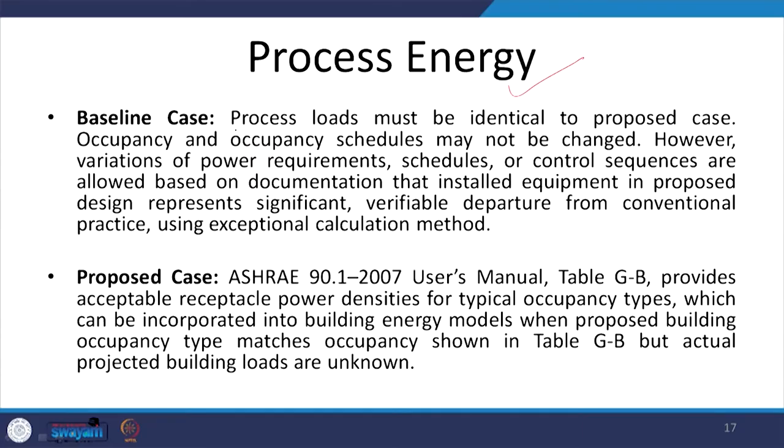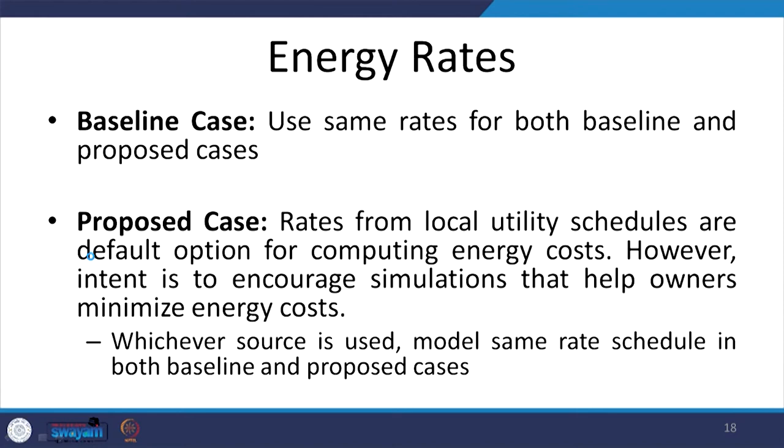Last is process energy. The process loads in the baseline case will be identical to that of the proposed case. So, wherever the process energy is being used for equipments, for other power requirements or other processes, it will be kept the same. However, the occupancy schedules for the controls may vary, but all other process loads will be kept identical for both the cases. In both the cases, the same rates from the local utility will be used as the default option for computing the energy cost.